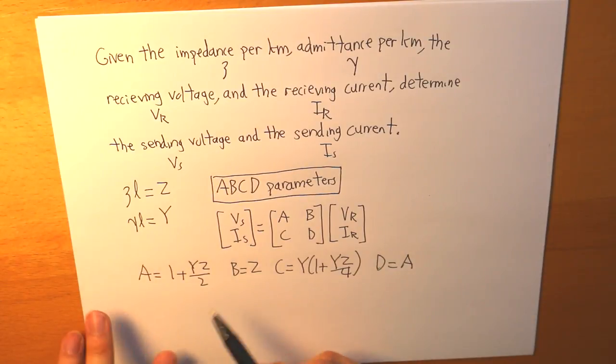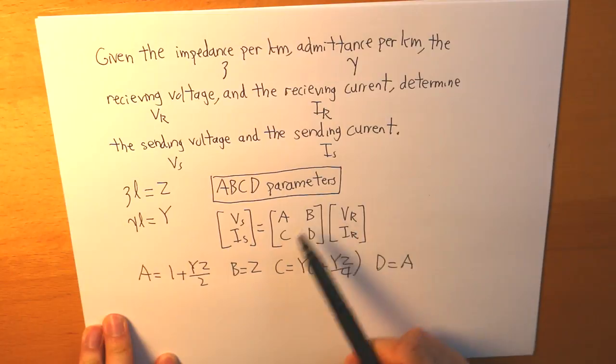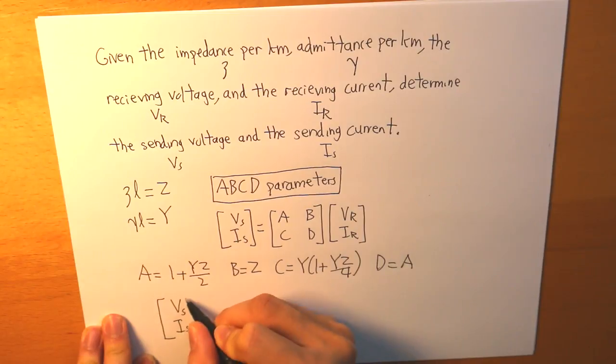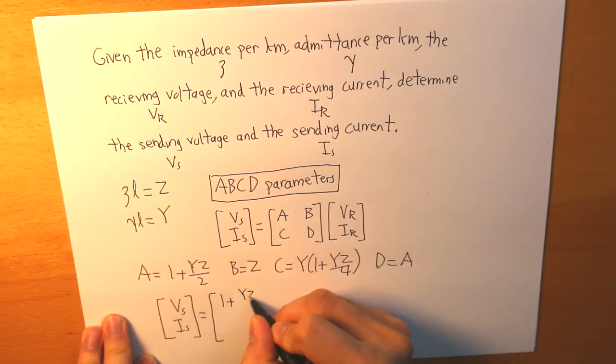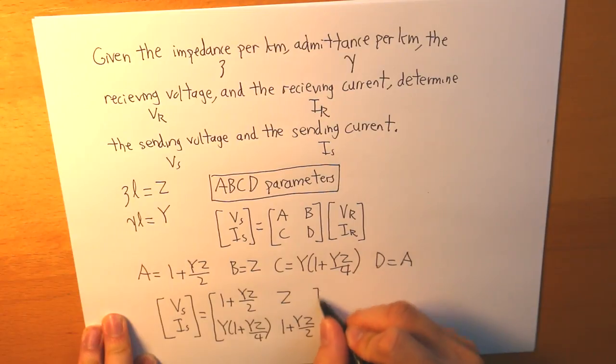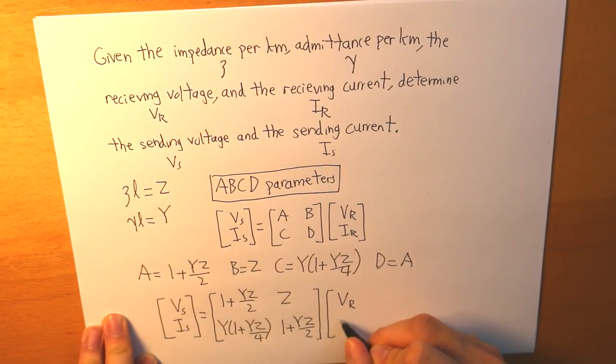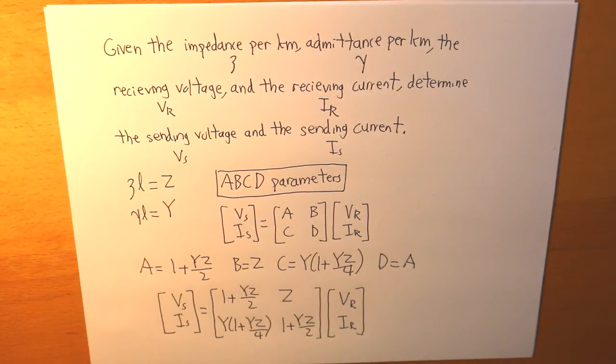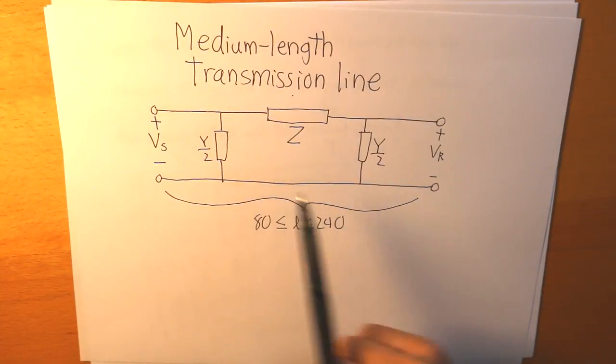And this is how our final matrix, our ABCD parameter, is going to look like. So, we have VS and IS. And then 1 plus YZ over 2. Z here, Y times 1 plus YZ over 4. And then we have 1 plus YZ over 2 here again. And then we multiply that by VR and IR. And this is what we get, our final equation on determining our sending voltage and sending current in a medium length transmission line.